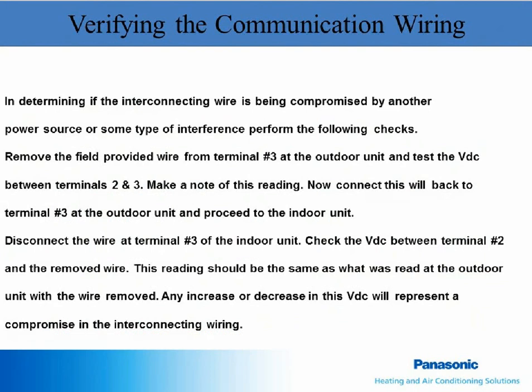Running the interconnecting wires close to high voltage or close to ballast or transformers can cause communication errors. If you're getting a communication error, the way you could check is go to the outdoor unit and remove the wire at terminal 3. Take a DC voltage reading between terminal 3 and terminal 2. Write it on a piece of paper and reconnect the wire and go to the indoor unit.